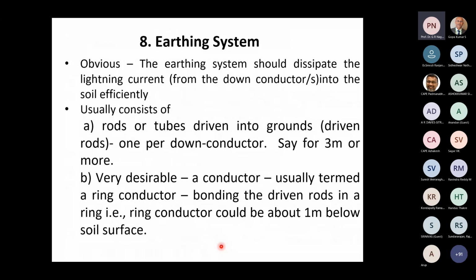Now, the earthing system is very obvious. It must dissipate and distribute the lightning current. Dissipate and distribute, both are very important. If there is no bonding between the earth ends, it will still dissipate, but it will not distribute over the whole area. The earthing system usually consists of rods or tubes driven into the ground, typically maybe 3 or 4 meters. There are again standards for that. One per down conductor is essential, say every 3 meters or more.